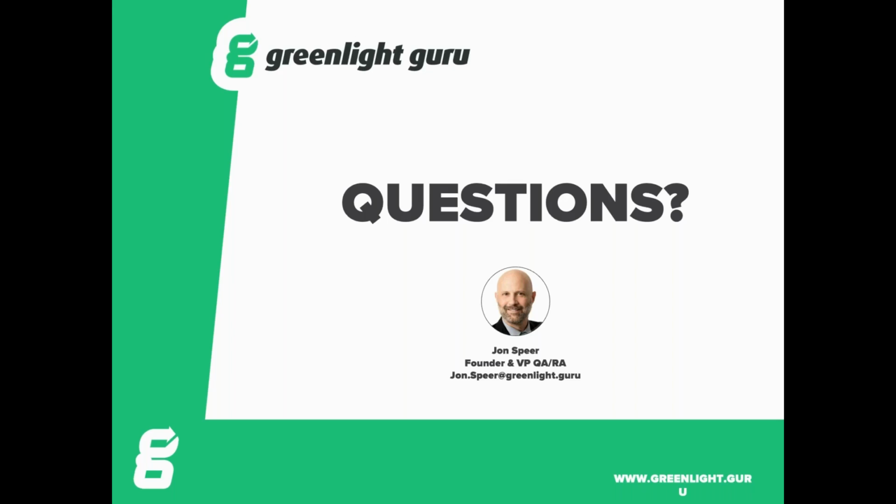Jamie, yes, you can do those sorts of things. The key thing will be, I guess, the first question I would ask you and to consider is, what type of testing are you doing to notice whether or not it's feasible? If it's verification testing, that might require some more, I guess, diligence, some more formality in how you go about this process. If it is just some benchtop early feasibility testing, sort of informal testing, if you will, there's still a need to document and capture your decisions that you make.